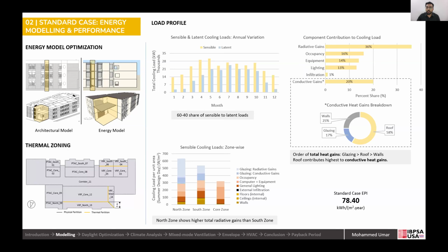Of course, because this is a warm, humid climate zone, 40% was dominated by latent loads. Coming to the zone-wise sensible cooling loads, the north zone shows an overall higher cooling load than the south zone, followed by the core zone. This is a little bit of atypical behavior because typically in the northern hemisphere we see the south zone showing the highest cooling loads.